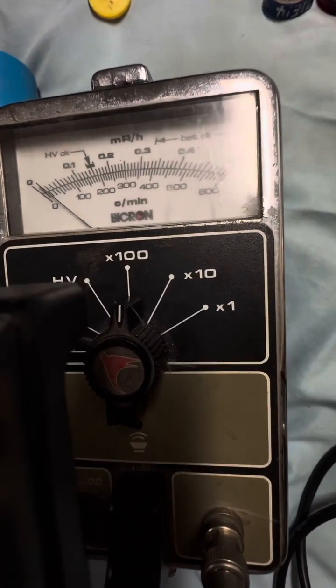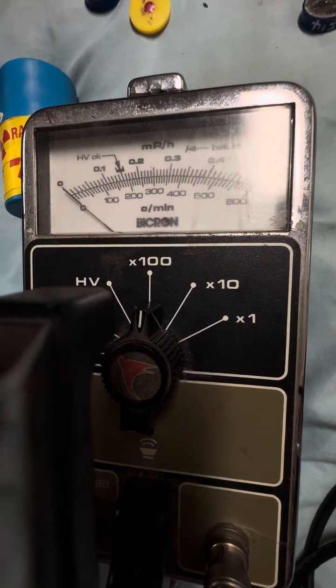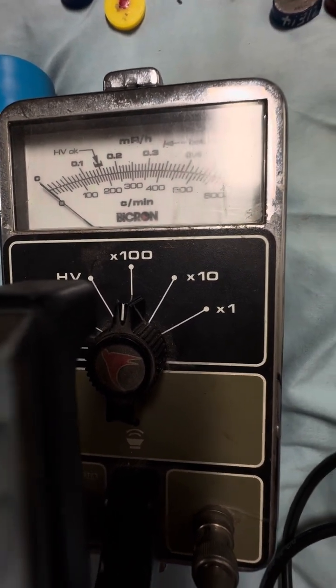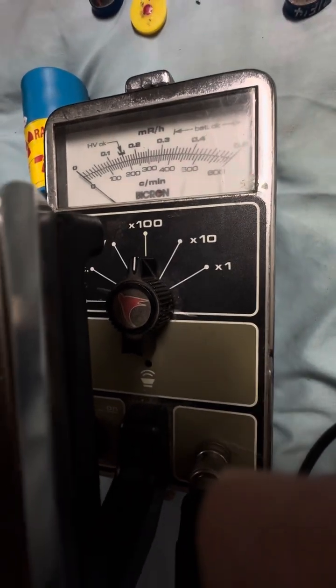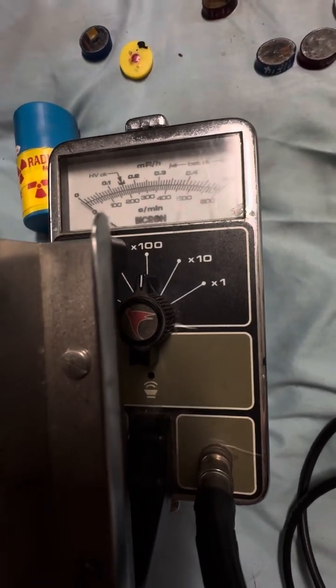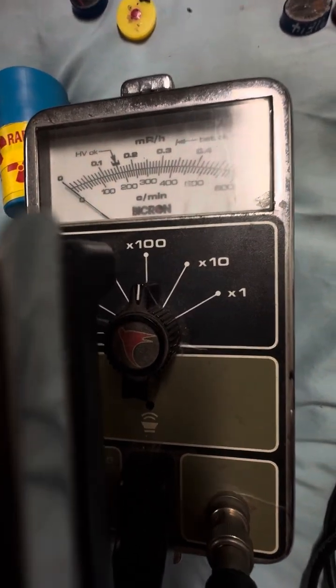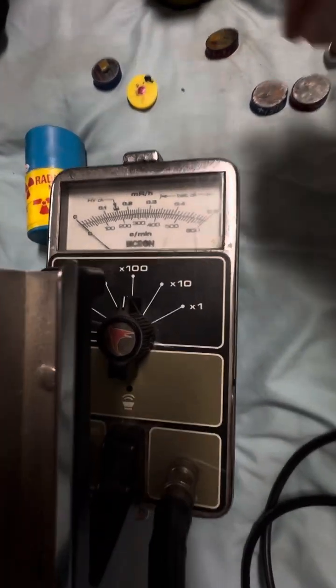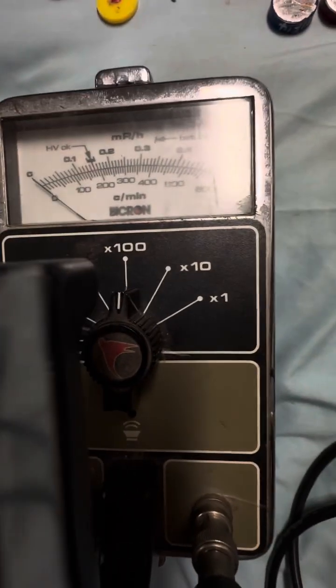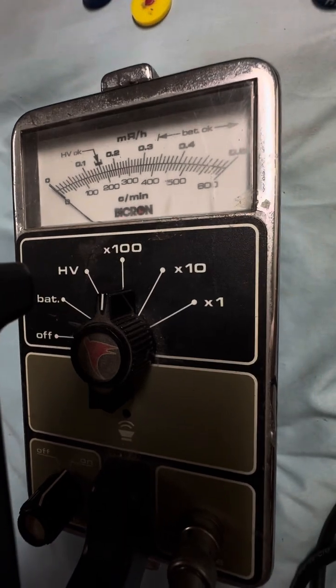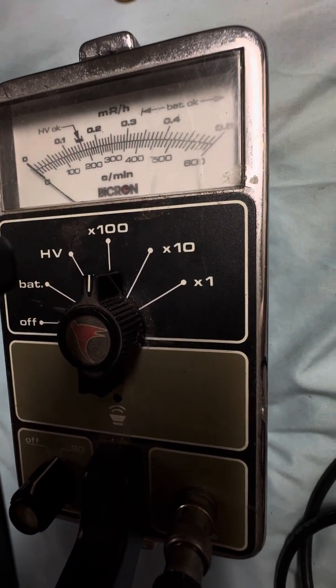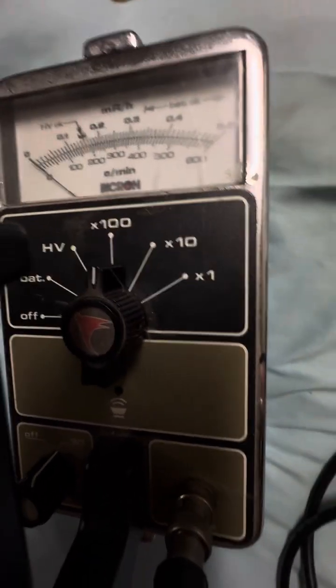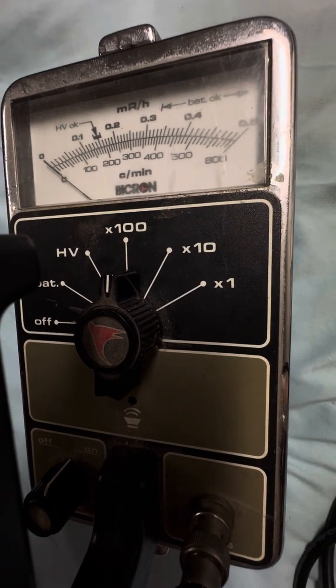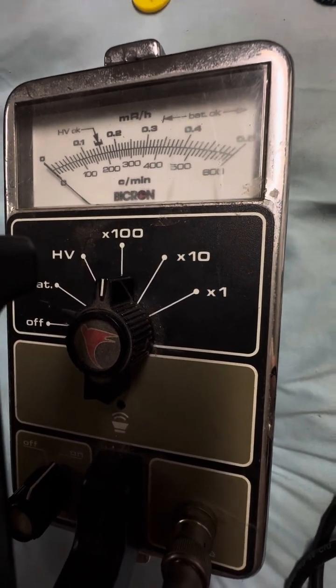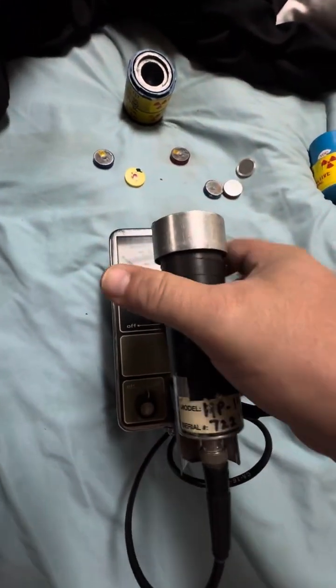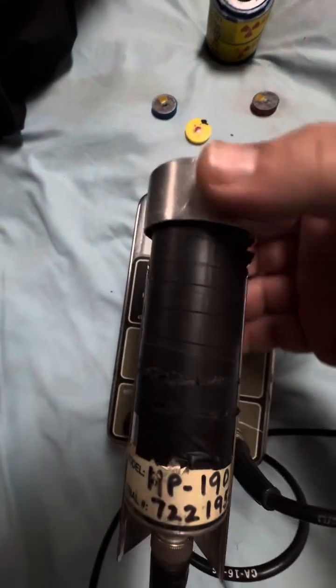So this has been calibrated. I just did it today on a pulse generator and with various sources and probes to specifications from Bicron. I didn't have the specific calibration procedure for this specific meter, but it's similar enough to the Surveyor M and Surveyor 50 that the calibration procedures are the same. So you're getting a perfectly calibrated Geiger counter. It is well below the 10% variance in readings when used on a pulse rate generator. So it can actually pass for Nuclear Regulatory Commission standards, which require less than a 10% variance of actual dose. So this is capable of being used as professional equipment. There's really no reason to not use it professionally.